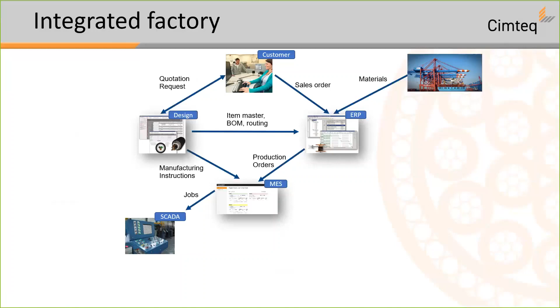Once it's in SCADA, the recipe gets downloaded to a PLC, which is basically an industrial computer inside your machine. The PLC will instruct the machine to set up for that batch of production, so it will set up all the temperatures for the extruders and instruct the drives to ramp up to achieve minimum waste, etc.